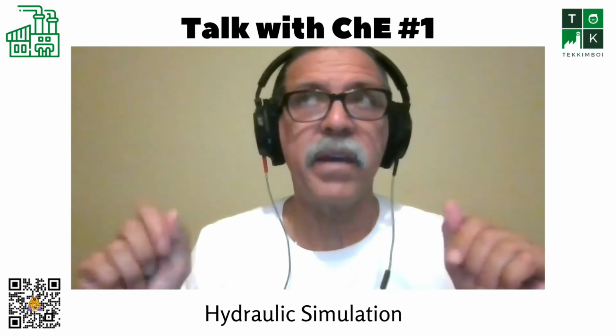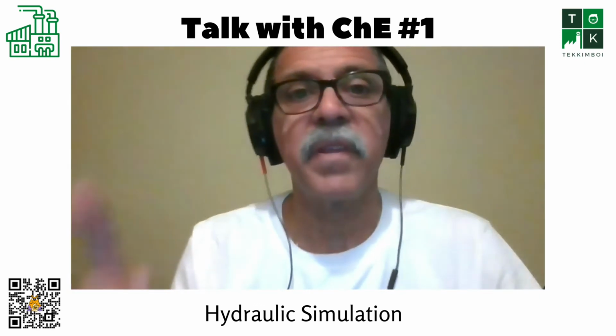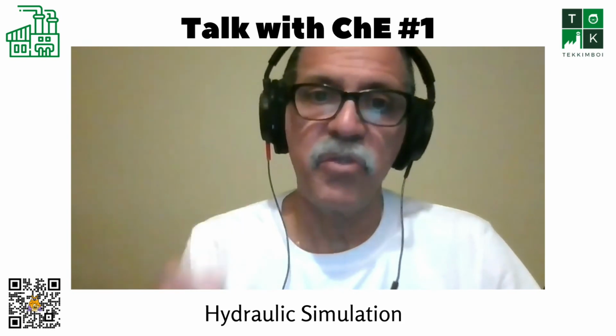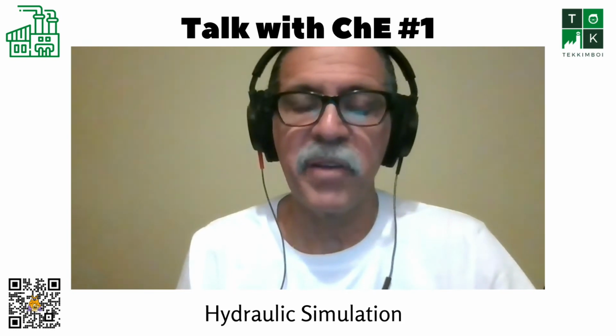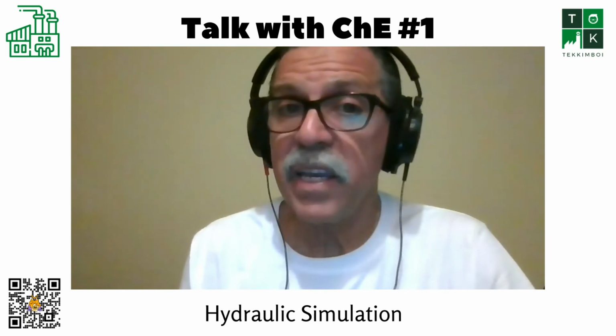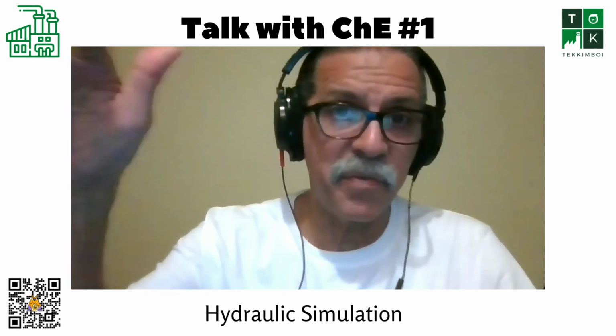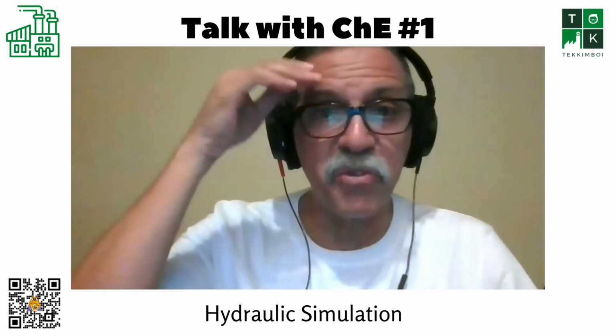And then you have to look at what is the best, let's say, recommendable location for the new service. Because depending on where you put or introduce this new service, you can balance or unbalance other services. Okay, and normally in this kind of circuit, the plants that have problems are the ones that are far from the source.